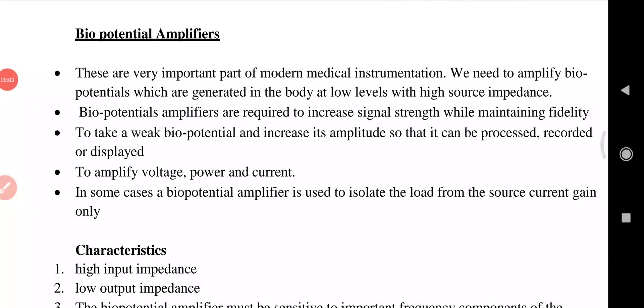Today we are going to discuss about biopotential amplifiers. Biosignal acquisition or amplification is a difficult task because it handles biosignal data in the low microvolt or low frequency region. In some cases, particularly EEG preamplifiers are required to detect signals as low as a few microvolts. The quality of biosignal acquisition in medical instruments is purely dependent upon the preamplifier design.